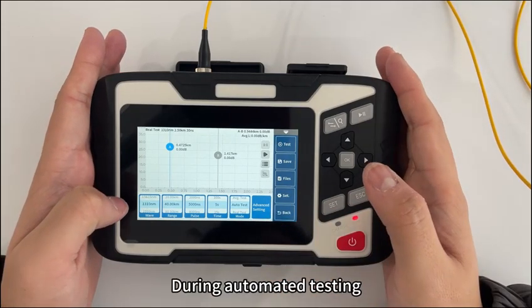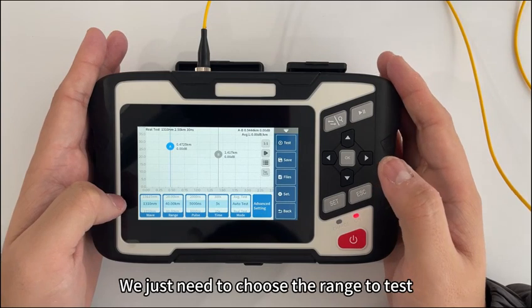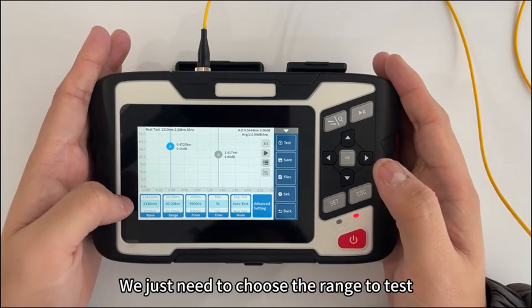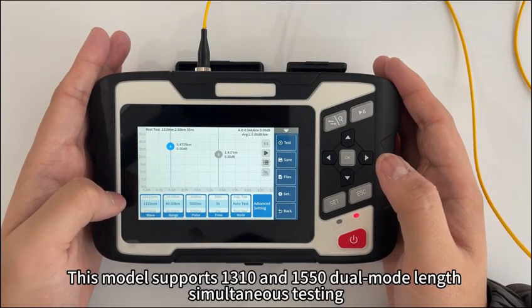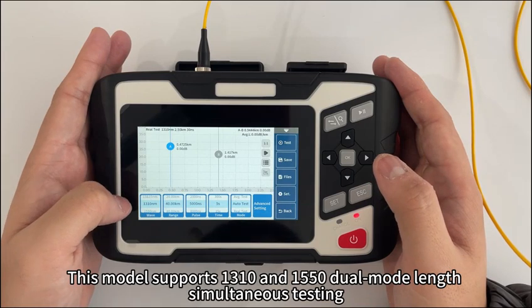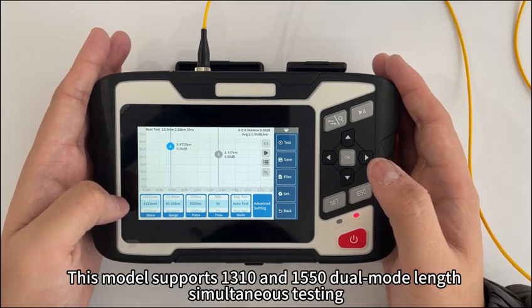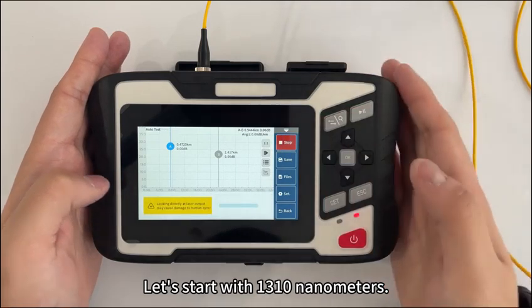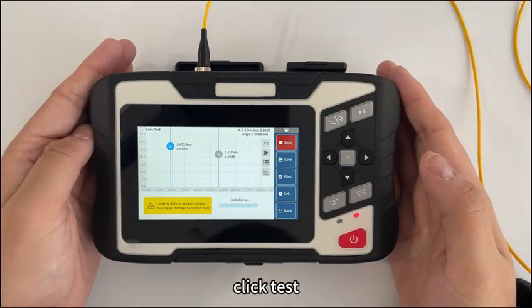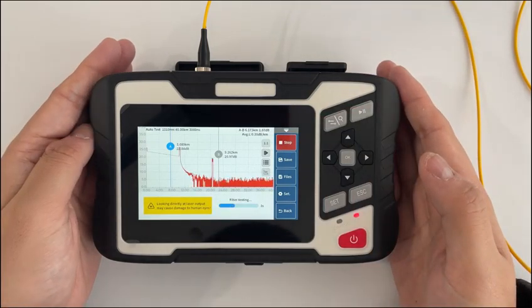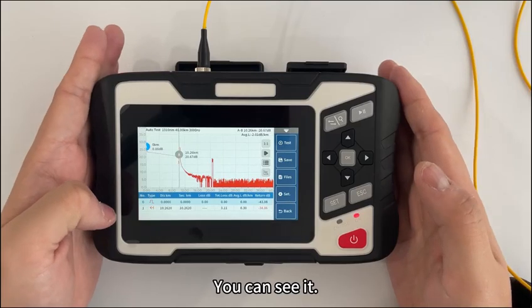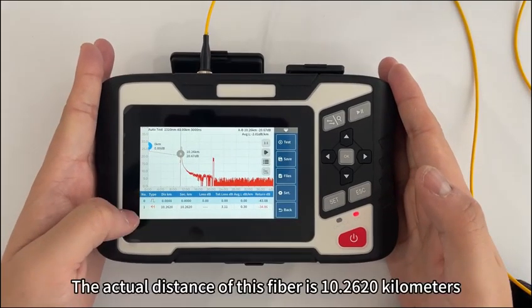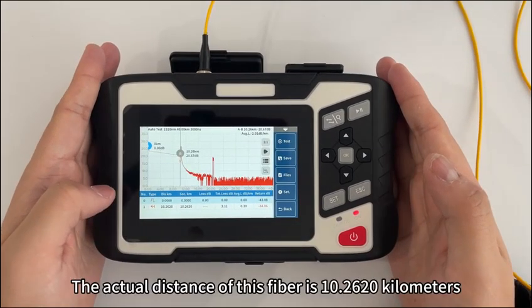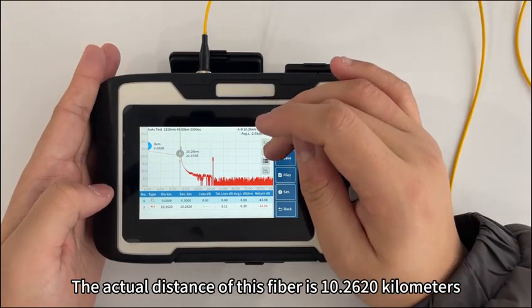During automated testing, we just need to choose the range to test. This model supports 1310 and 1550 dual wavelength simultaneous testing. Let's start with 1310 nanometers. Click Test. You can see it. The actual distance of this fiber is 10.2620 kilometers.